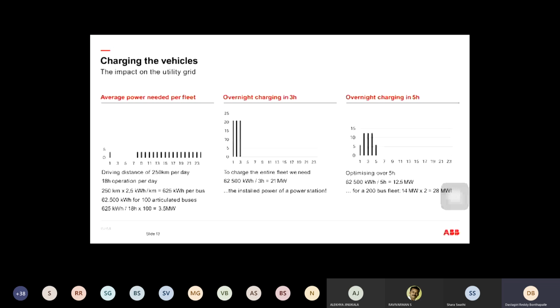Now what is the impact on the grid? Let's consider a bus with 18-hour operation, running roughly 250 kilometers per day, assuming an 18-meter bus. The energy needed is 250 kilometers into 2.5 kilowatt hour per kilometer, giving 625 kilowatt hour per bus.